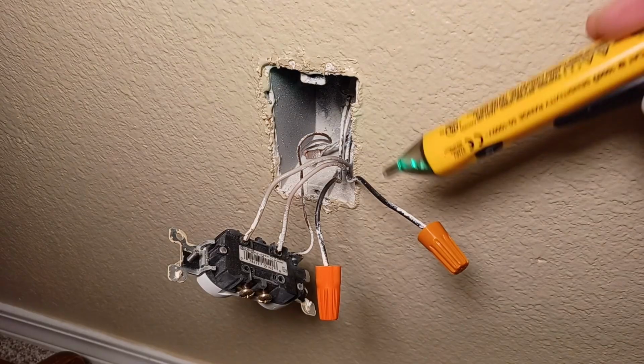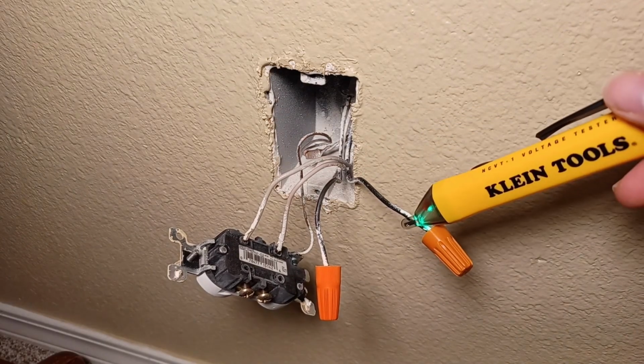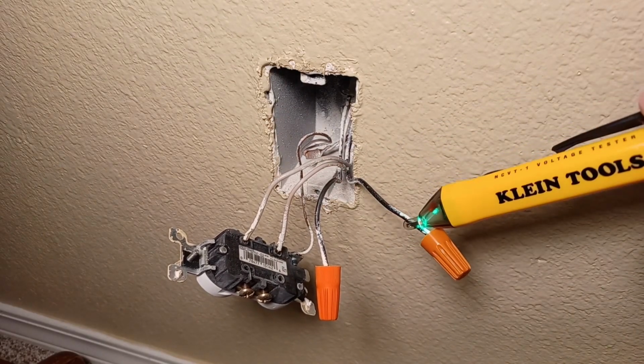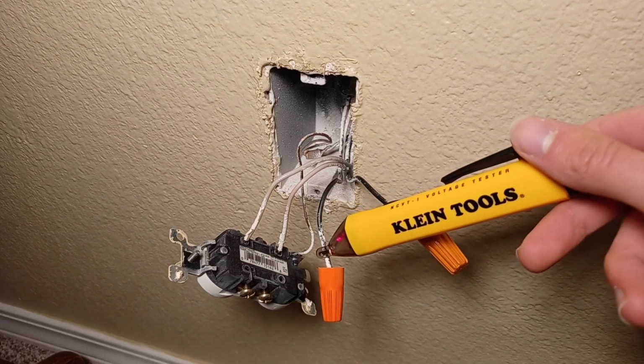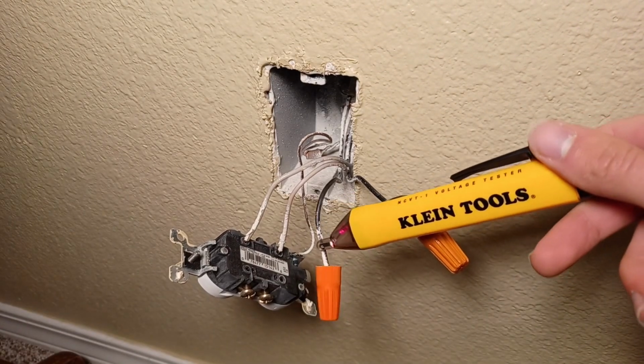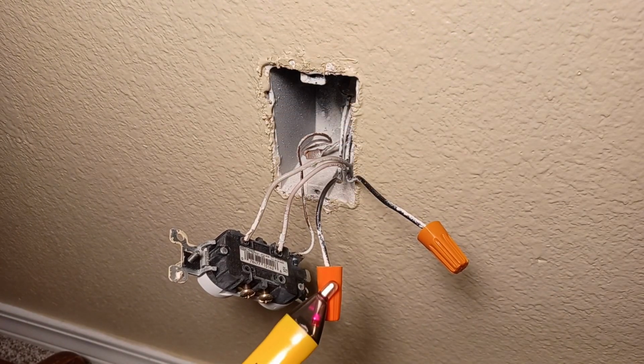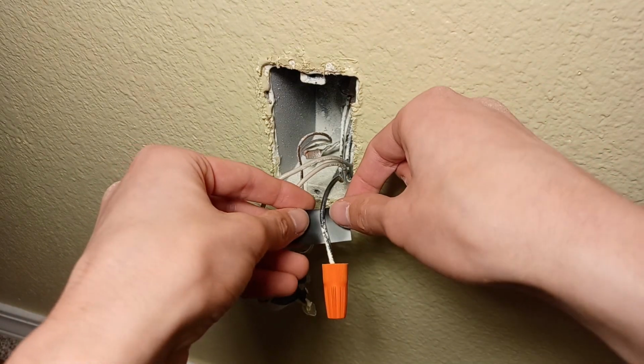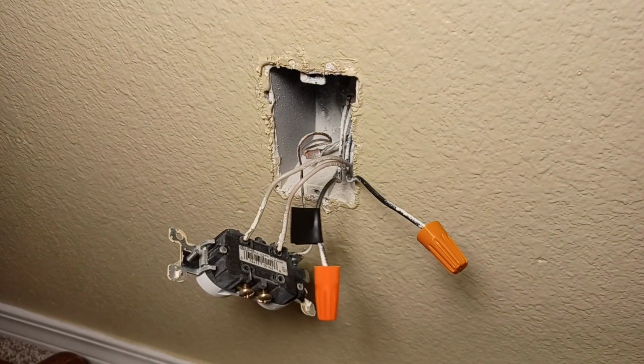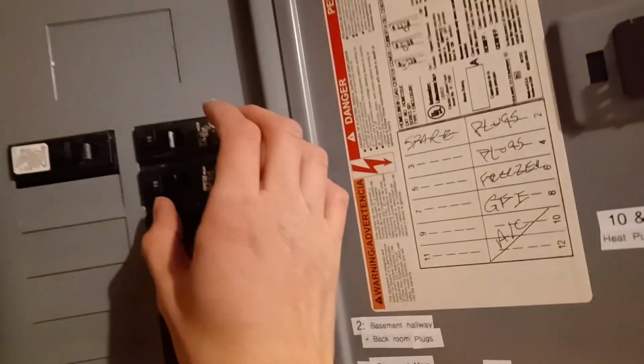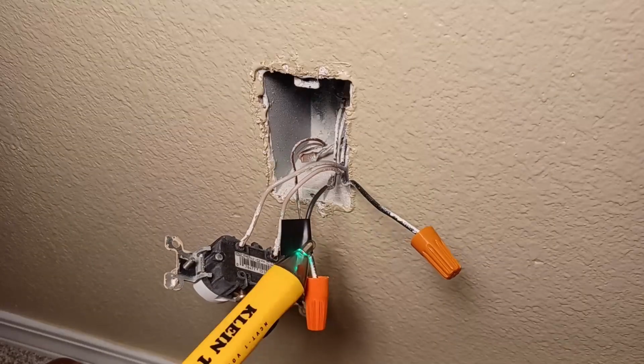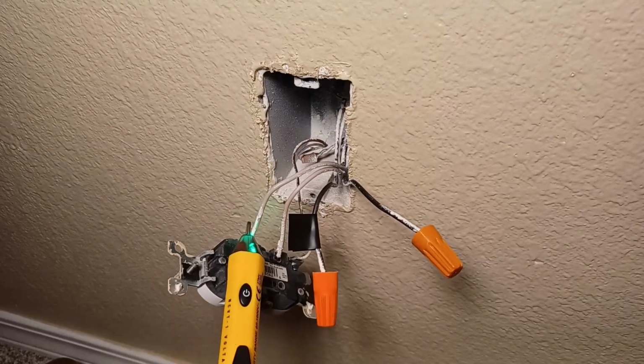outlets. This can be done with a non-contact voltage tester. This one does not trigger the tester, so this is the load, which goes to all the other outlets. This one does trigger the tester, so it is the line side from the panel. So I will mark it with some tape. This is important because the line and load side on the GFCI does matter. And then, once again, the breaker must be turned off. And then none of these have power, so we're good.